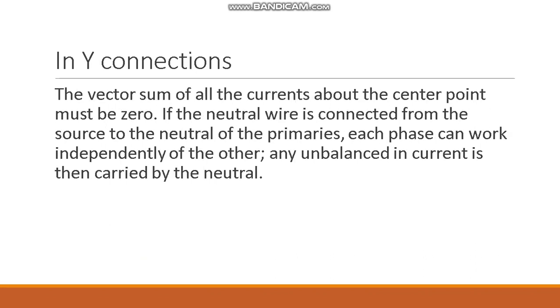In Y-connections, the vector sum of all the currents about the center point must be zero. If the neutral wire is connected from the source to the neutral of the primaries, each phase can work independently of the other. An unbalanced current is then carried by the neutral.